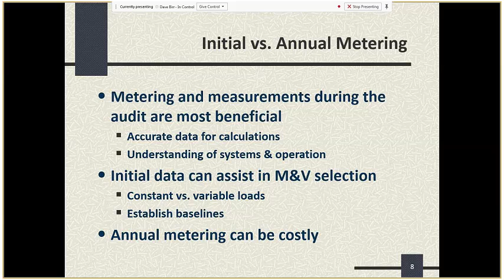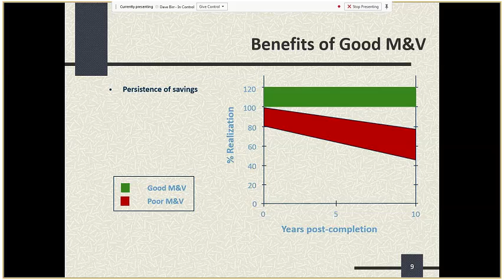So what are the benefits of good M&V? With good M&V, shown by the green line, you can see savings rise over the 100% mark, maybe as high as 120% over time. With poor M&V, you might see savings degrade over time, losing as much as 20 or 30 percent as the years roll by, as controls fall out of calibration or equipment isn't properly maintained or operated—losing the opportunity to avoid future utility consumption. The goal is to maintain the original design performance of the equipment and prevent drift or degradation of controls or inherent efficiency.